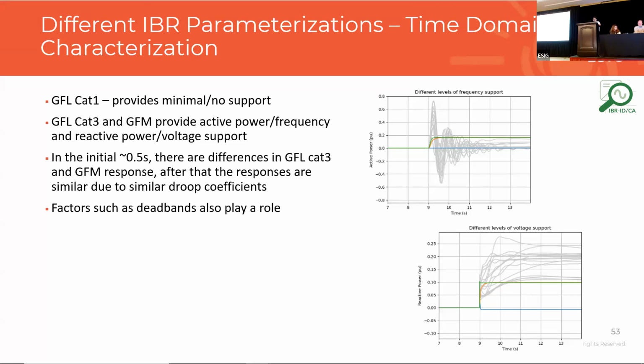The reason for that reduction in response is essentially that the resource is consuming some reactive power service from the network for a voltage change. It's minimal, it's small, but it's still reducing. The reason for that is it depends upon where these services are observed. Take an inverter-based resource plant: it has the inverter or the turbine, transformers, collector networks, and then maybe another transformer for the plant transformer, and then the final point of interconnection on the transmission bus where it connects.